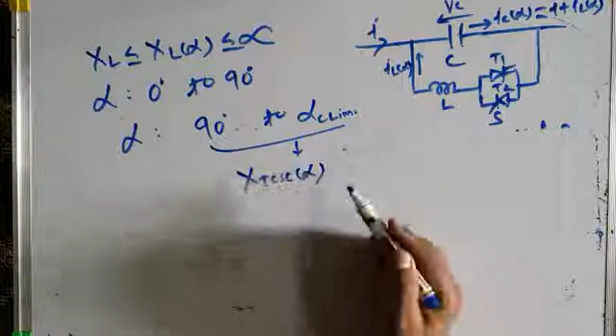So therefore, this alpha, that is the TCR delay angle, we can divide into two ranges. One is alpha which varies from 90 degrees to some lower value. Let's call that alpha C lim, where lim means lower limit of alpha. And during this, your TCSC reactance, as you have just seen, is capacitive in nature. At alpha equal to 90 degrees, TCSC reactance is minimum, that is equal to 1 by omega C. As alpha is decreased from 90 degrees to alpha C lim, your TCSC reactance becomes more and more capacitive. It goes on increasing till alpha C lim. If alpha is decreased below alpha C lim, then parallel resonance will occur.